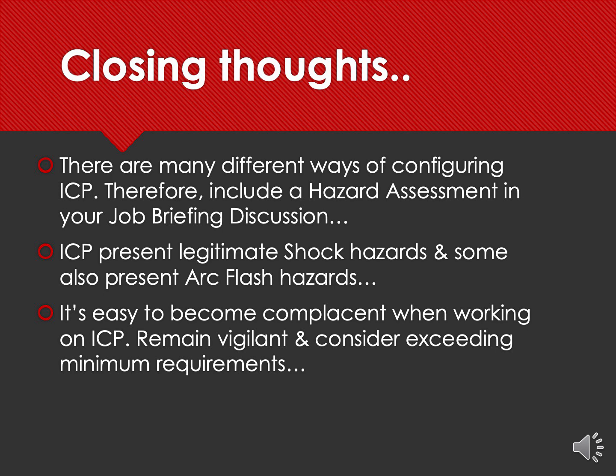This is so because especially in situations when you're troubleshooting, a piece of equipment may have failed catastrophically inside the panel or inside the piece of equipment, and the normal switching procedures would no longer apply. In those situations, the qualified electrical worker will have to come up with what we call a special precautionary technique, and they will come up with an alternative system of achieving equivalent protection in that situation. I recommend that you have that kind of discussion when working on industrial control panels because each one could be quite different from the other ones, even in the same part of the plant.